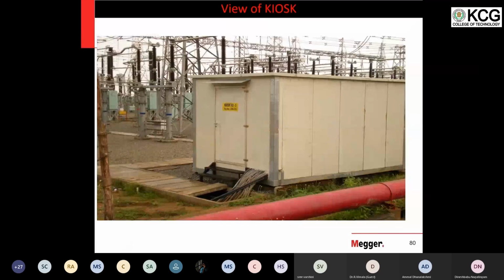Okay, kiosk. In the earlier slides, starting with the switchyard pictures, I was telling you that there is something called a kiosk. What is a kiosk? So this is called a kiosk. A kiosk is a room which is kept in the switchyard. What is there inside the kiosk? The relay panel is there inside the kiosk. So this is how the kiosk will look. This is not very latest technology. If you have an opportunity to visit any power grid substation or even TNEB substations, at the level of 400 kV and above, 765 kV like this, you will definitely find this kiosk available. Most of the substations constructed after 2006 are with kiosk technology. When I say most of the substations, I mean 400 kV and above.